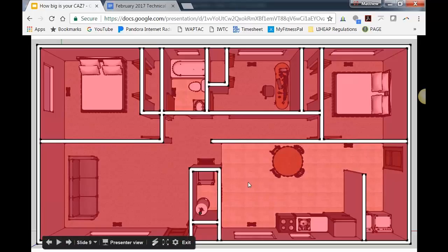That's perfect. We need to have enough combustion air for this appliance, and so when you calculate the volume of the space that it could draw its combustion air from, this space minus all the bedrooms and bathrooms has to be large enough to allow for that. Is that right? Yes. Perfect.